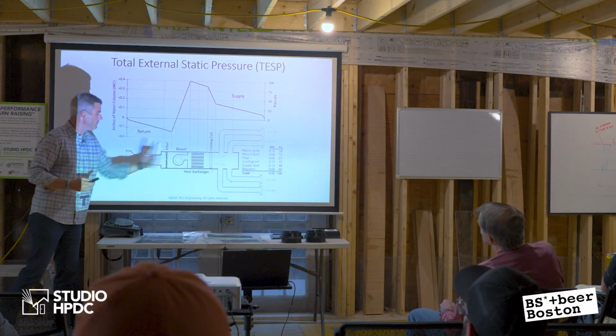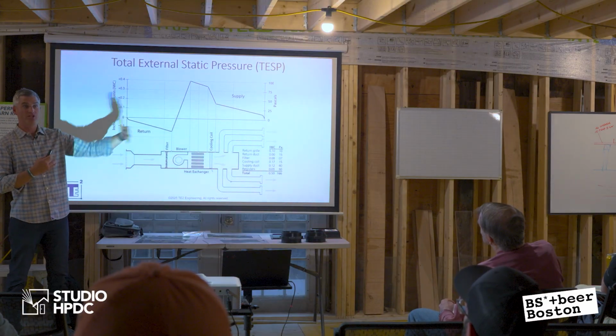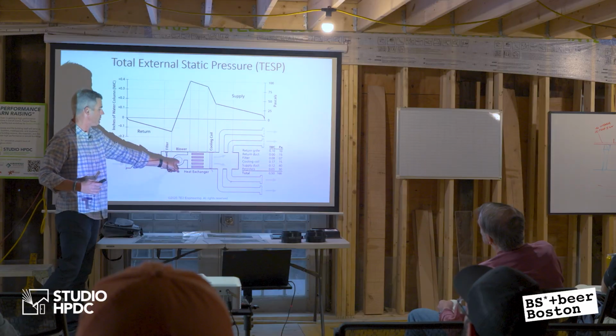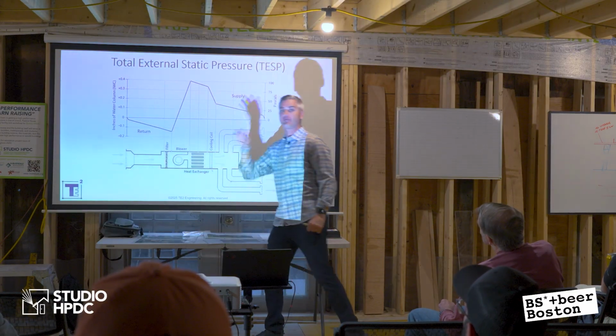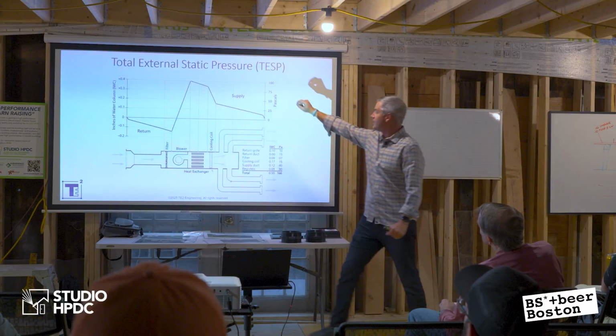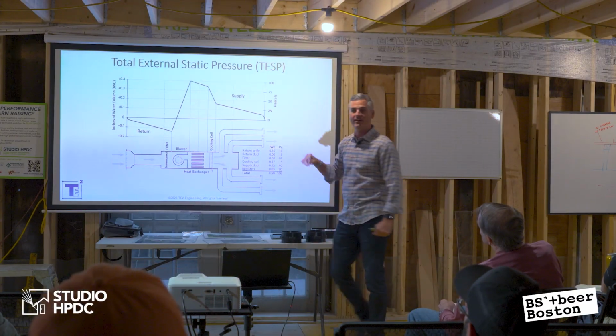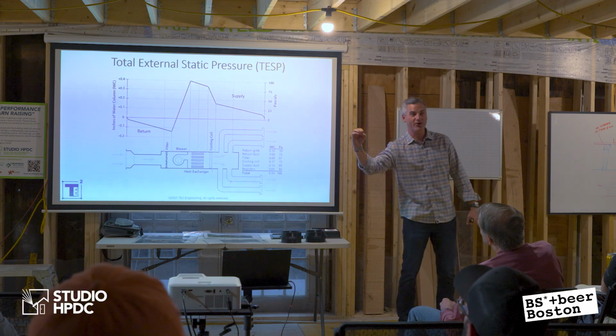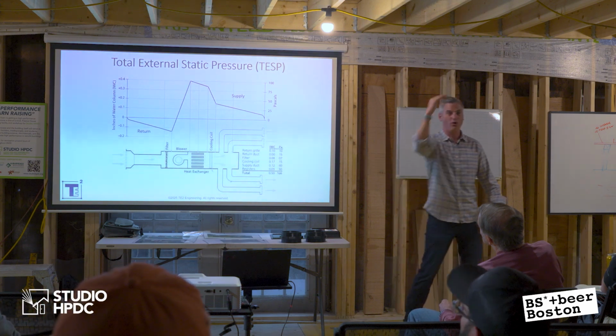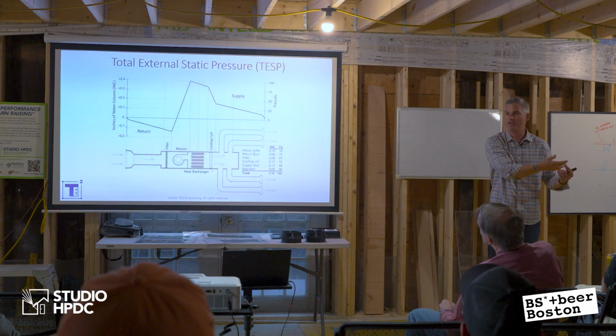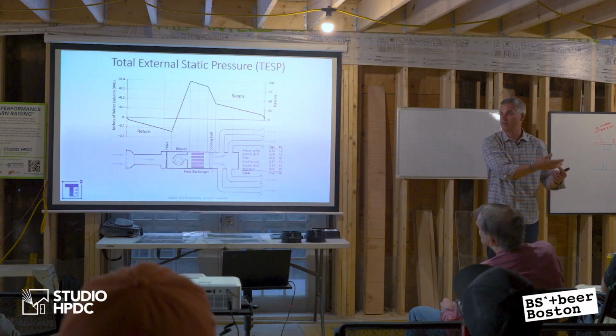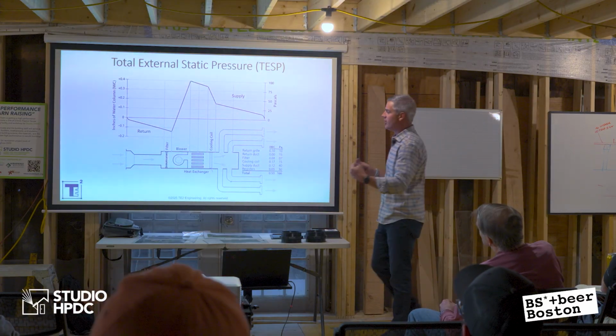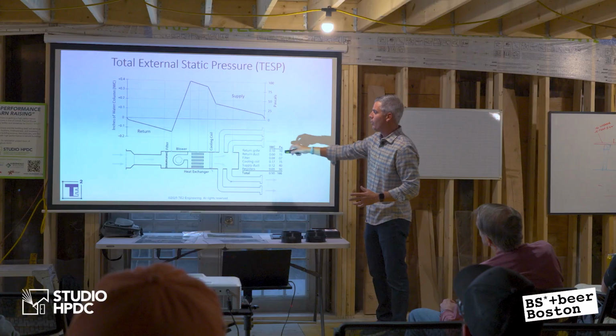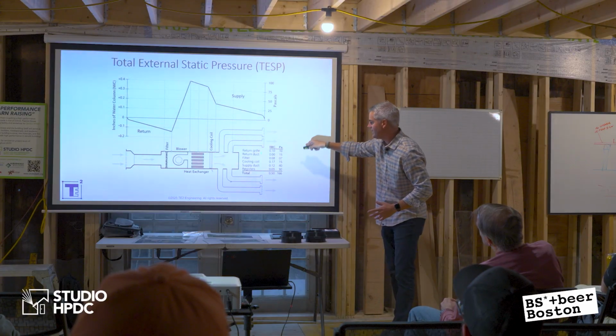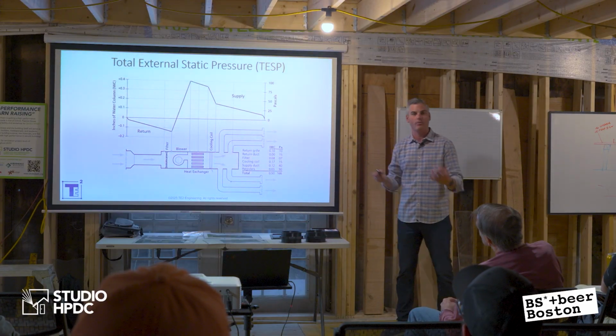And then the blower does its job. It imparts static pressure. It builds the static pressure. And so this is the boost. The blower does the boost. So the highest pressure I'm going to see is right on the discharge of the blower. That's my highest static pressure. And then guess what? Then I have the decay all the way back to 0. So it starts at 0 pressure in the room. It goes through the whole duct system. It comes out at 0 at the other end. Did everybody see that? So when we talk about duct sizing, we want to make sure that all of these components, everything here, are mapped out and calculated for appropriately.